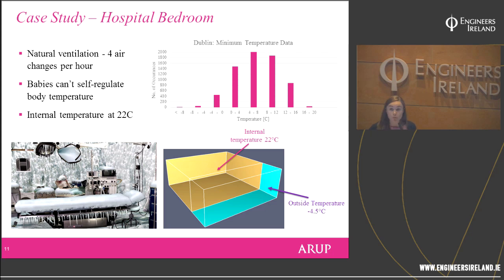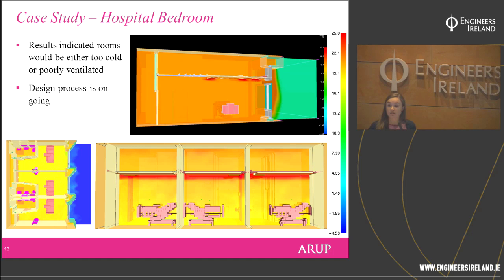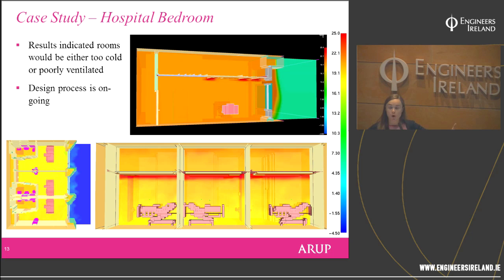We analysed local temperatures using an appropriate outdoor temperature of approximately minus four and a half degrees in winter. Our model included heating panels, radiant heating panels on the suspended ceiling, various extraction points, fans in ensuite toilets, and the louvers. We found that the bedrooms would not be warm enough — at best around 17 or 18 degrees Celsius with windows open in winter. These results demonstrate the problems of placing heating panels on a suspended ceiling near openings.